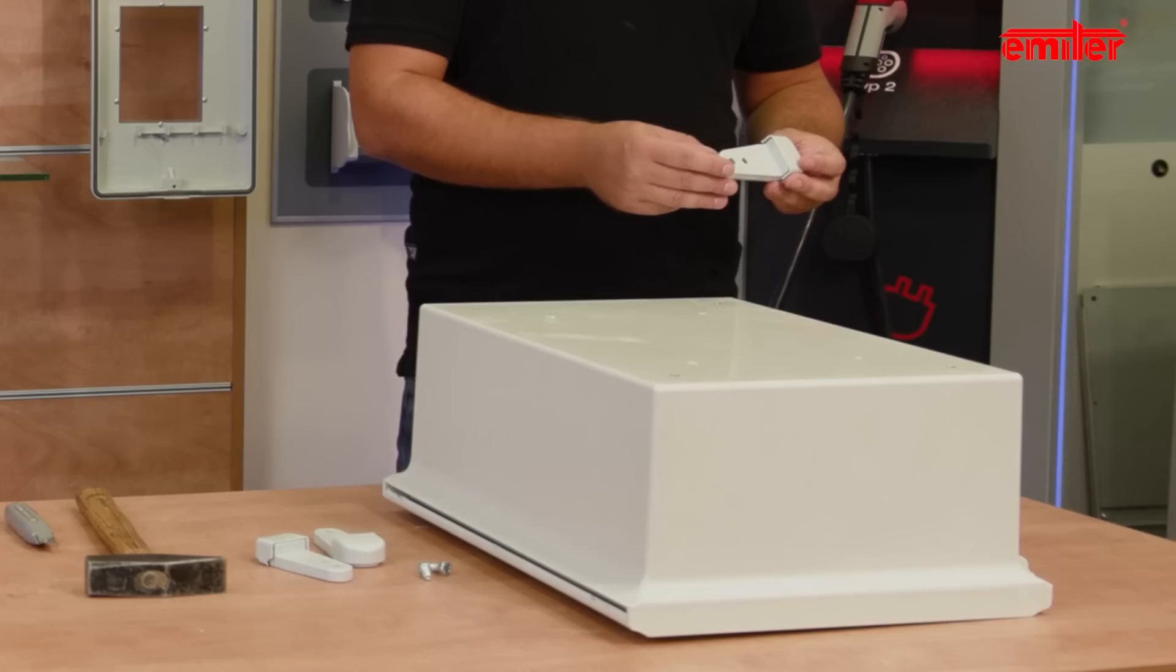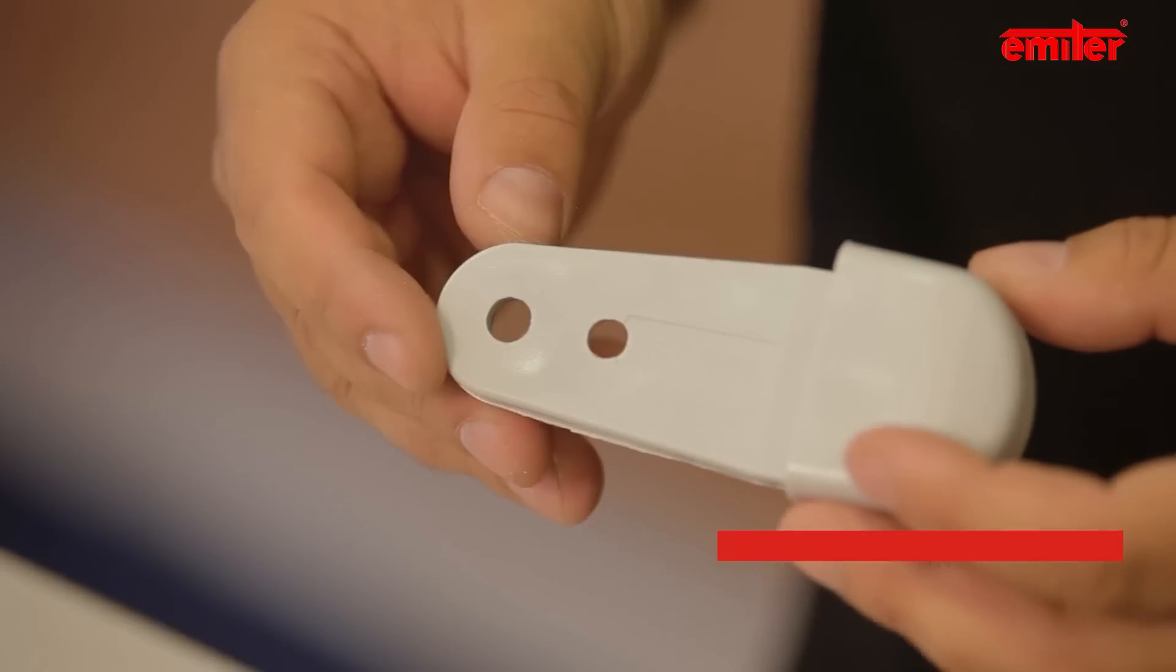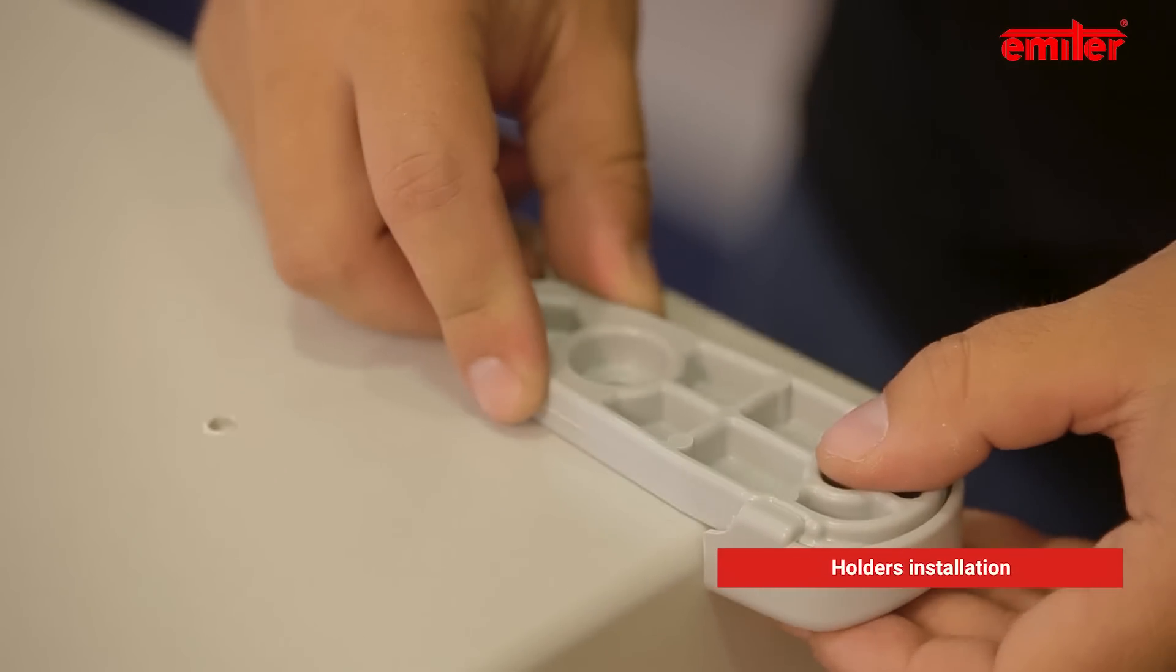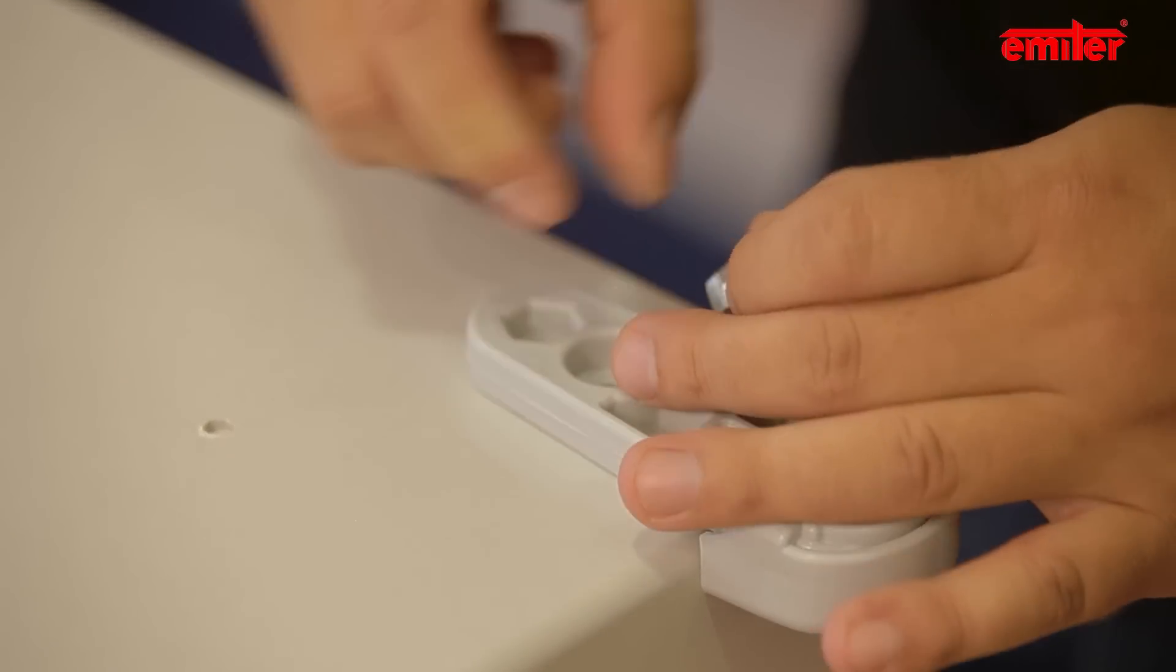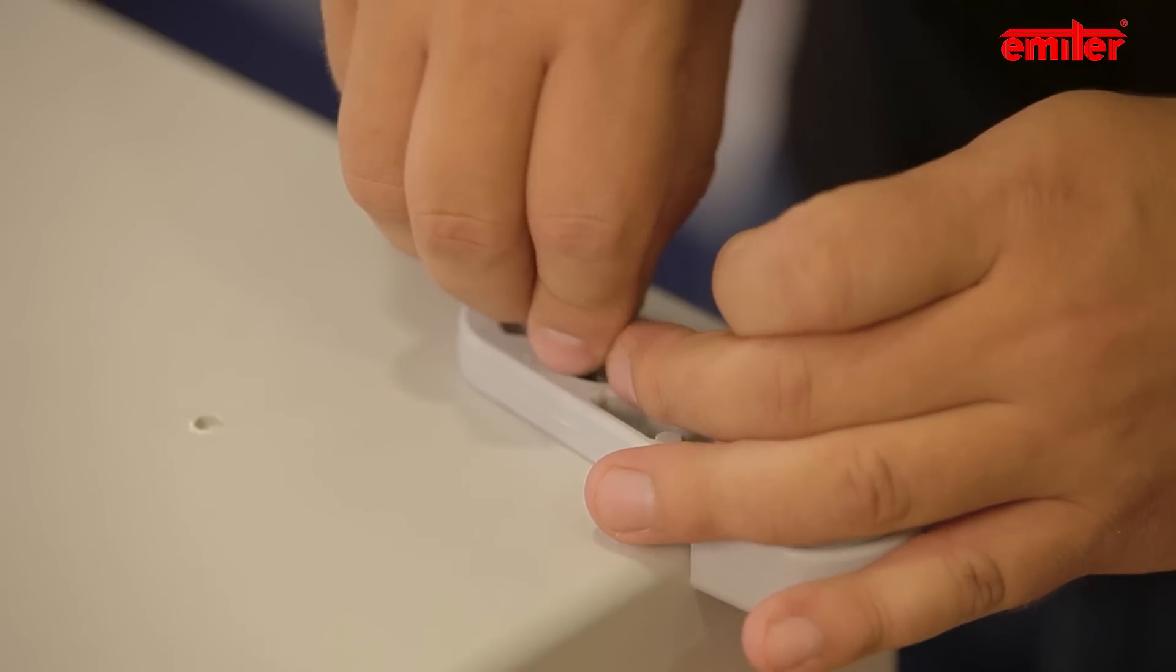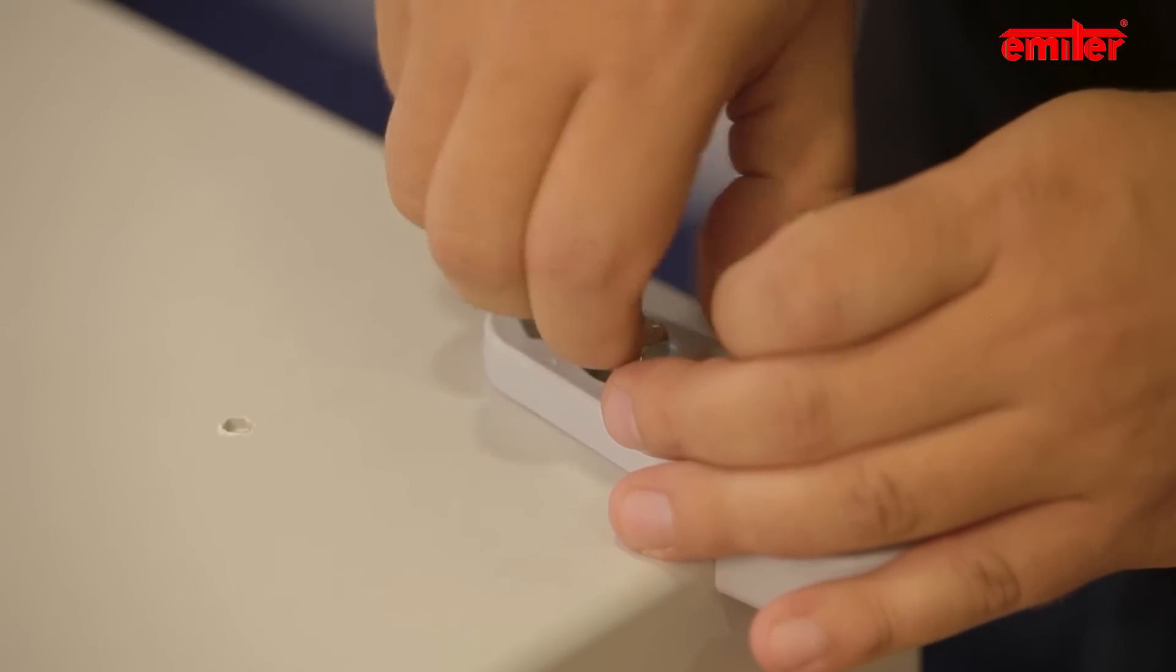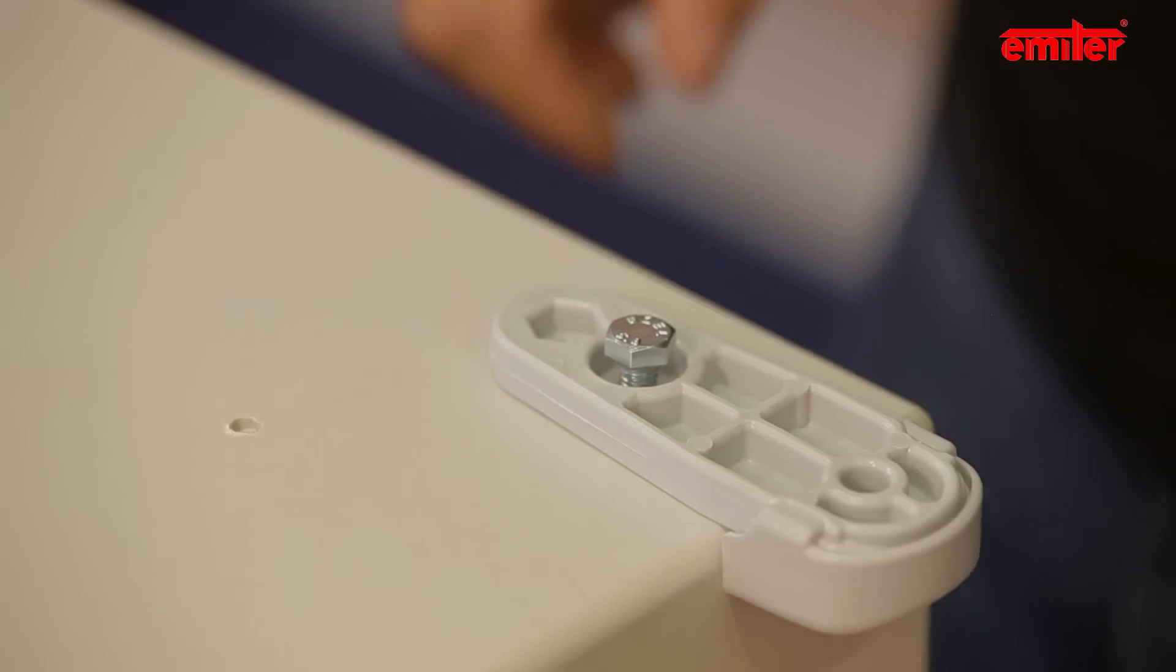Sleeves are installed. Now we can mount the holders. For this purpose, we use four bolts M8x16, which are part of the set. We attach the holder in the way its retaining surface adjoins the side wall of the enclosure, and the holes match with the axis of the previously installed sleeve.